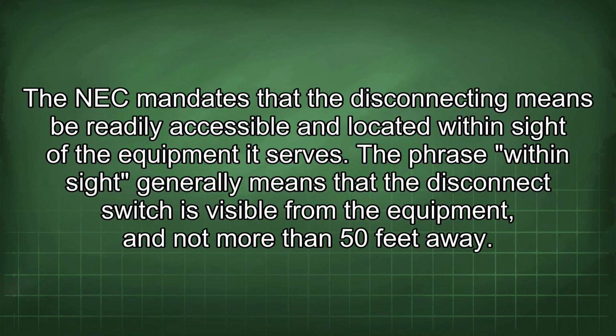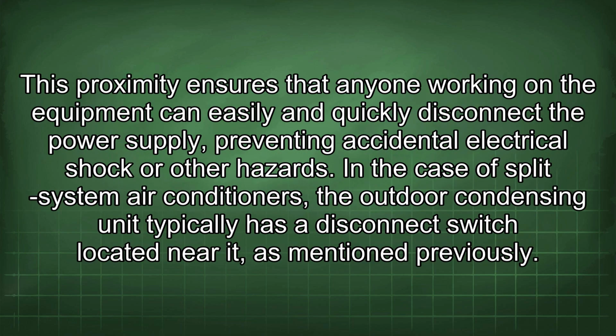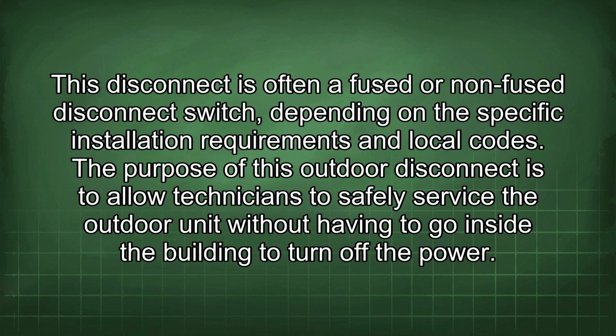The NEC mandates that the disconnecting means be readily accessible and located within sight of the equipment it serves. The phrase "within sight" generally means that the disconnect switch is visible from the equipment and not more than 50 feet away. This proximity ensures that anyone working on the equipment can easily and quickly disconnect the power supply, preventing accidental electrical shock or other hazards. In the case of split-system air conditioners, the outdoor condensing unit typically has a disconnect switch located near it, as mentioned previously. This disconnect is often a fused or non-fused disconnect switch, depending on the specific installation requirements and local codes. The purpose of this outdoor disconnect is to allow technicians to safely service the outdoor unit without having to go inside the building to turn off the power.